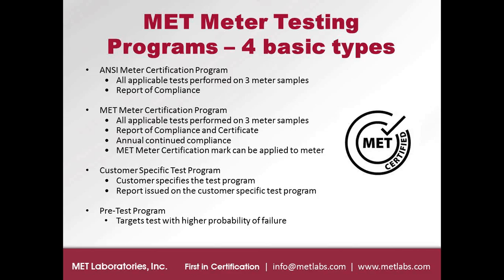Now, if you have a family of products that are very similar in design, maybe the currents are different or they have a different voltage range, then the standard does allow you to combine at least one of each type or each feature of that meter family to create your 3 sample set. Sometimes there are more than 3 samples, but at the very minimum, if you only have one type of meter, one type of build, you're going to need to run 3 samples for each test. So at the end of that ANSI Meter Certification Program, we're running all the applicable tests, and you'll get a report of compliance for that.